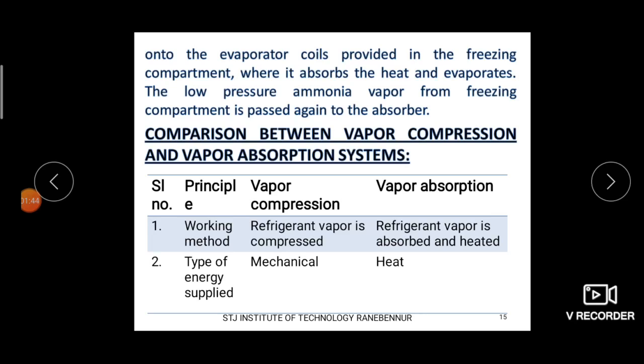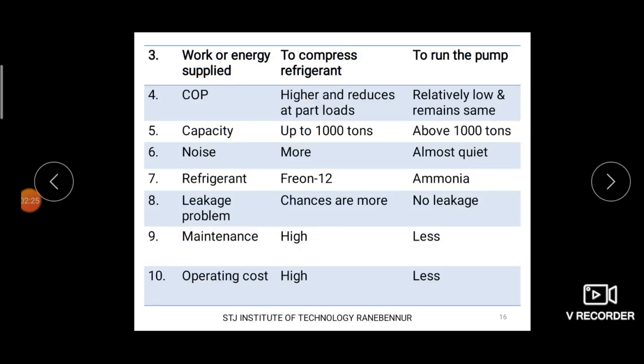The next difference is the type of energy supplied. In case of vapor compression refrigerating system, we make use of mechanical energy in order to operate the compressor. In case of vapor absorption refrigerating system, we make use of heat energy — in the heater-cum-separator, a heating coil is used to increase temperature. In the VAR system, we also make use of one pump, so we can say both heat energy and mechanical energy are used.